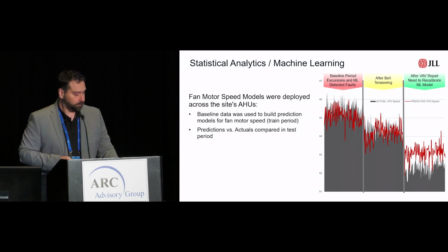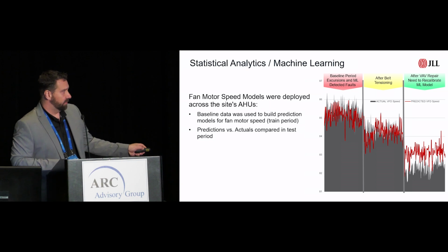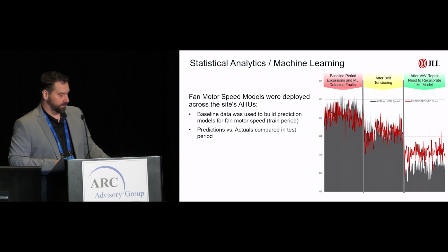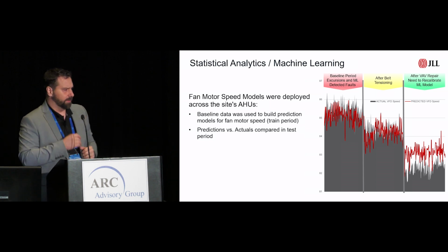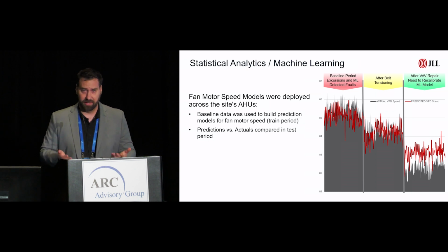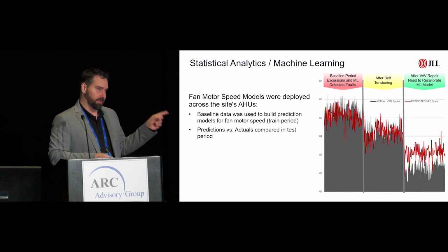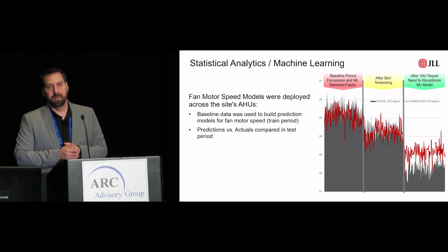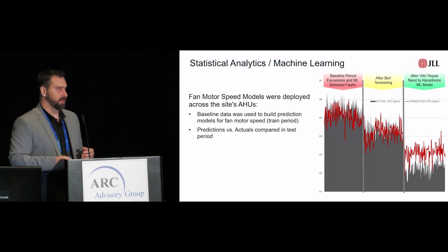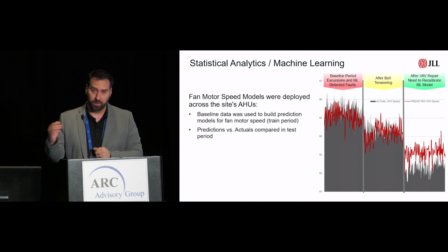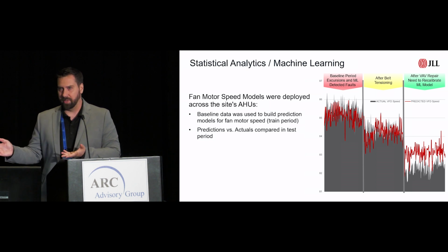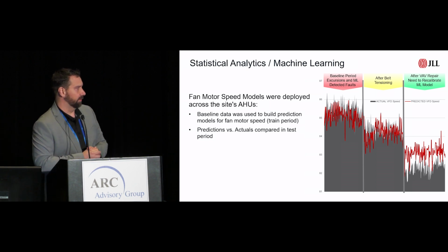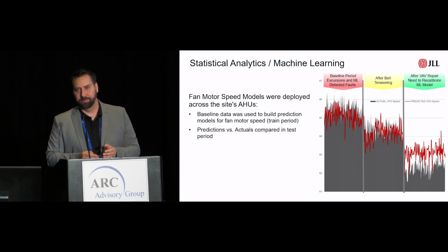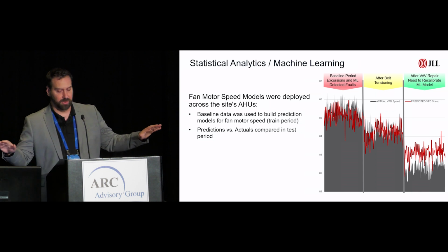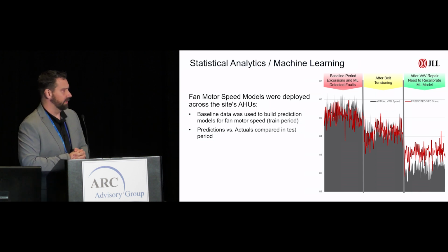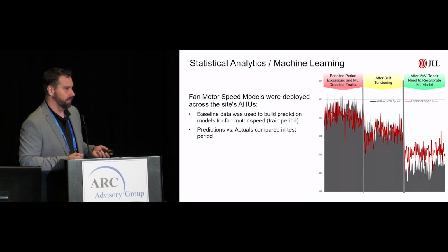And after we did that, we got what you see on the right-hand side. Suddenly, what the system thought we needed versus what we actually did. And this is where it gets into a lot of what we heard over the last couple of days about sustainability. This got the attention of every sustainable person within that 50-mile range of that unit. Because when we talk about reliability and asset management, we said we need to fix this so we don't have to replace the motor. We need to lubricate properly so we don't have to replace the bearing. These are cost avoidance measures, right? That was real world, live, instant energy savings to the tune of millions per year when it was actually taken and applied across all of those air handling units on that system. So it very quickly became, oh, thank you.